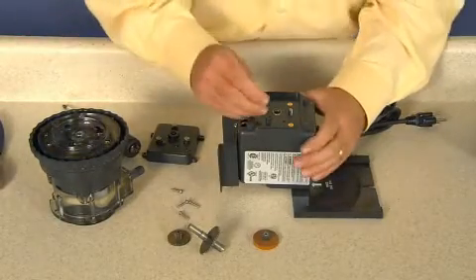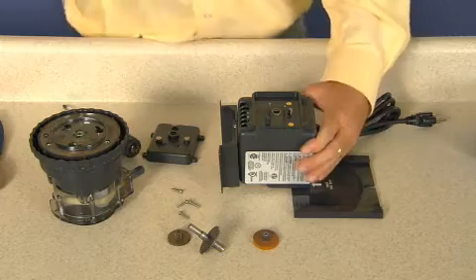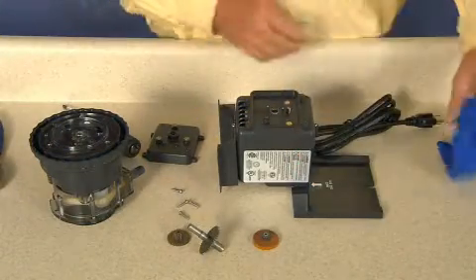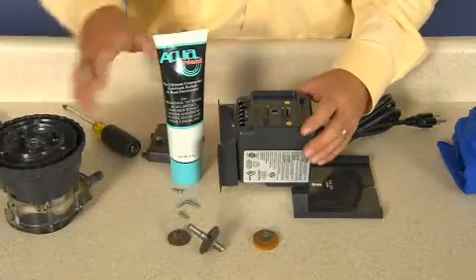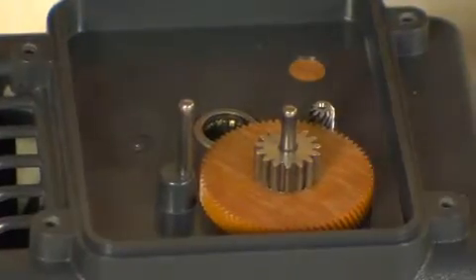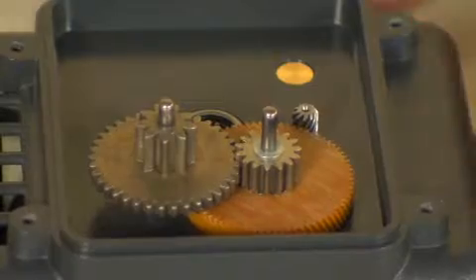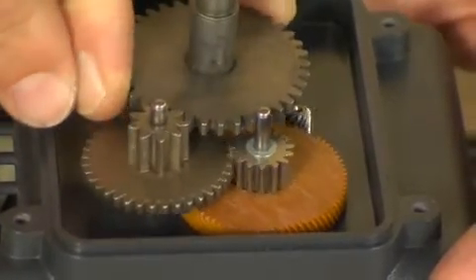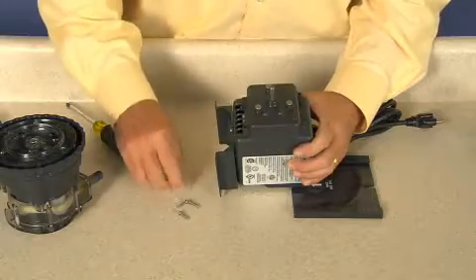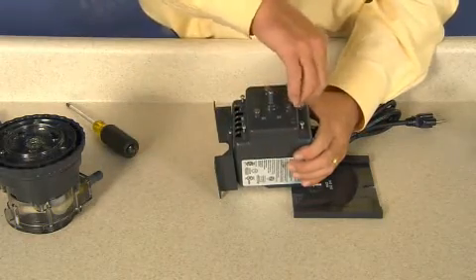Install the gear post by tapping with a rubber mallet until bottomed. Apply AquaShield on the new gear post before installing gears. Install the phenolic gear and spacer. Reattach the gear case cover with four new screws, finger tight only. The self-tapping screws must be backed out to locate the original threads before securing, to prevent stripping the screw boss.